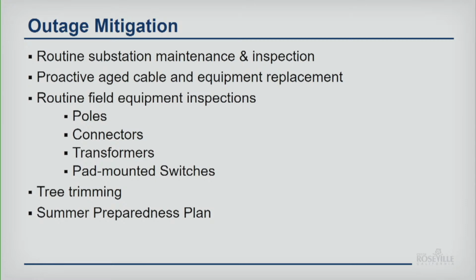We collect data on the age of the cable that failed and the manufacturer, and we look for trends to see which cable is having issues, and we proactively identify those sections and replace them. We do the same thing with transformers and switches if we're noticing any specific areas of concern. Also, with the rest of the distribution equipment, we do routine inspections. Every piece of equipment in our system has to have a visual inspection once every 5 years. So we're continually inspecting our equipment to keep up with that.